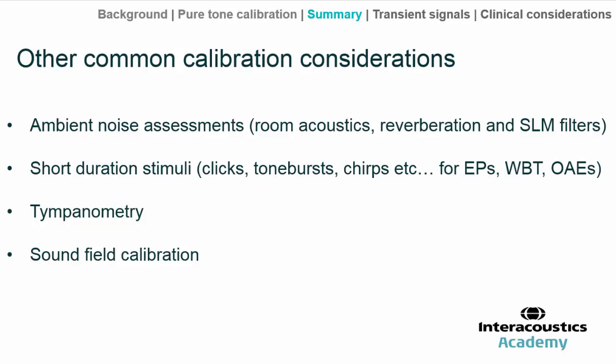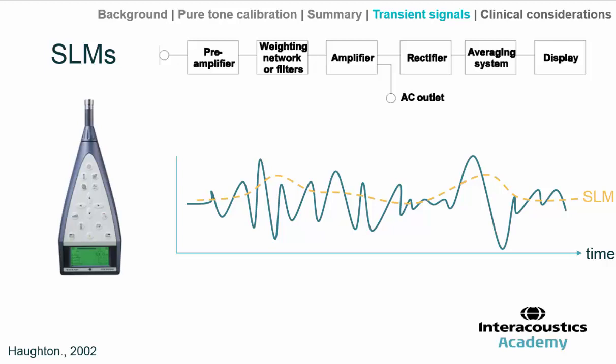For short-duration stimuli there's a marked difference in the approach. When it comes to sound level meters, many sounds measured by an SLM commonly fluctuate — speech sounds and other environmental sounds — not so much the pure tones we've been discussing, which are a very stable and relatively easy-to-measure signal. But many other types of signals that an SLM might be expected to measure fluctuate.